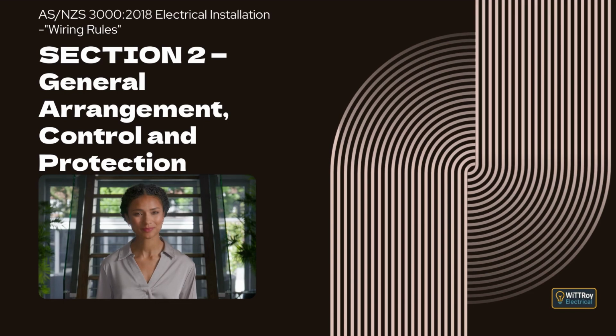Clause 2.5.2 Devices for protection against both overload and short-circuit currents. This clause explains the requirements for devices that protect against both overload and short-circuit current. The device must be able to break any overcurrent up to the maximum prospective short-circuit current at the point where the device is installed. It must also meet all the requirements of the overload and short-circuit protection clauses in Section 2.5.3 and Section 2.5.4.